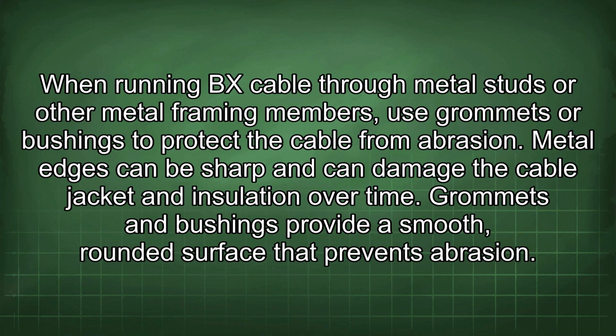When running BX cable through metal studs or other metal framing members, use grommets or bushings to protect the cable from abrasion. Metal edges can be sharp and can damage the cable jacket and insulation over time. Grommets and bushings provide a smooth, rounded surface that prevents abrasion.